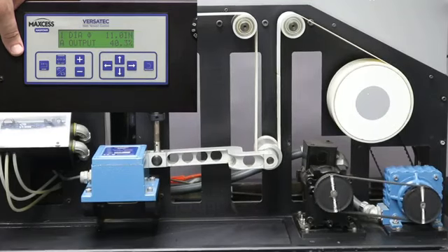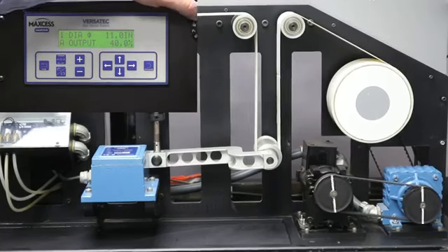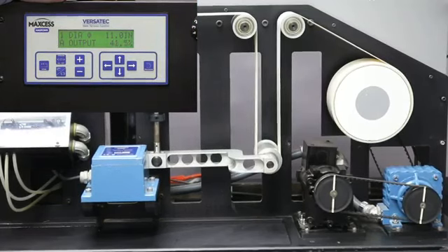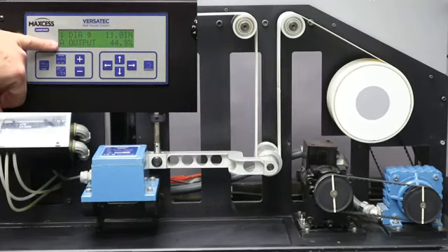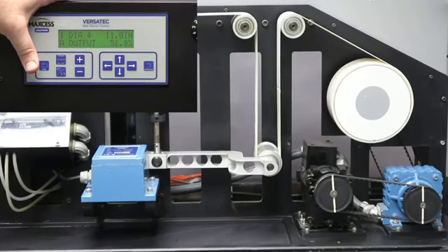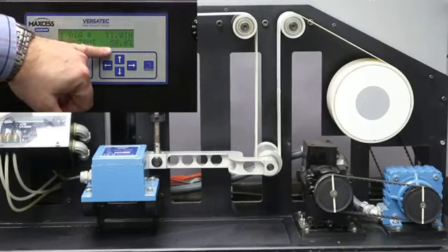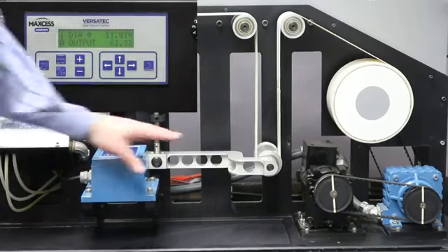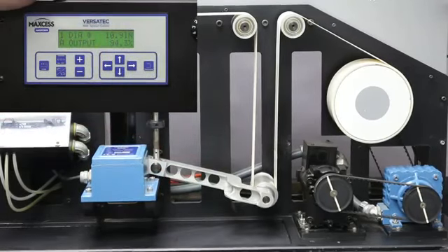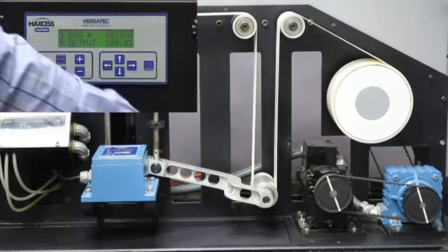If I were to stop this machine, so let's just stop the machine. Okay, so everything stopped moving. I turned the motor off, but I did not turn the control loop off. Note that I'm still in automatic. This control does not know that the machine has stopped because I didn't tell it. And you can see it's integrating up right now through 60%, and if it had stopped low, it's going to go even faster. So right now, the operator has stopped the machine just by stopping the web.